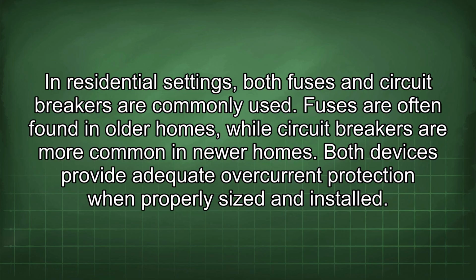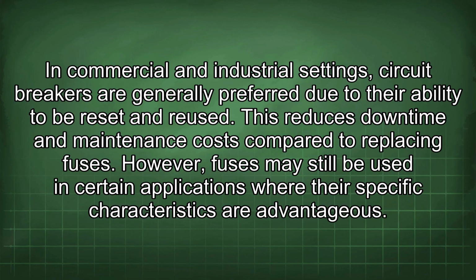In residential settings, both fuses and circuit breakers are commonly used. Fuses are often found in older homes, while circuit breakers are more common in newer homes. Both devices provide adequate overcurrent protection when properly sized and installed. In commercial and industrial settings, circuit breakers are generally preferred due to their ability to be reset and reused. This reduces downtime and maintenance costs compared to replacing fuses. However, fuses may still be used in certain applications where their specific characteristics are advantageous.